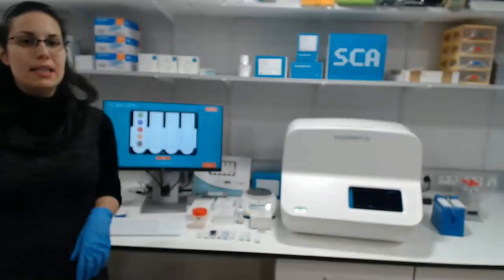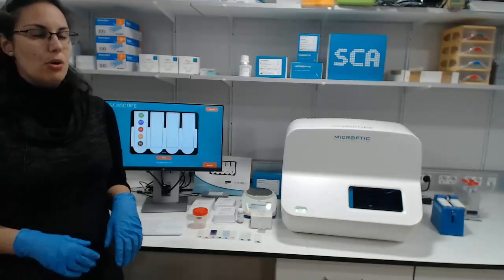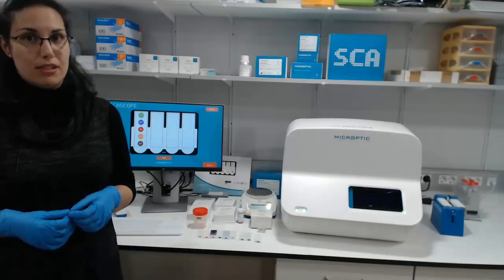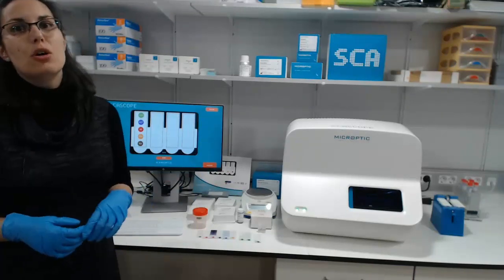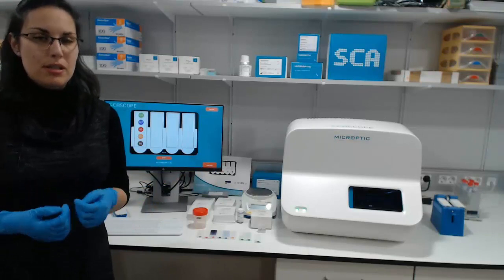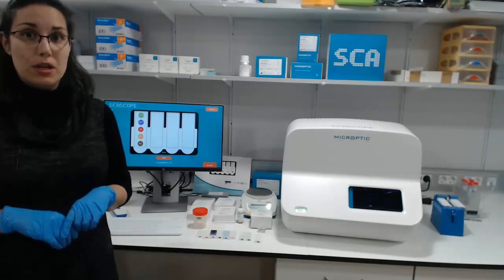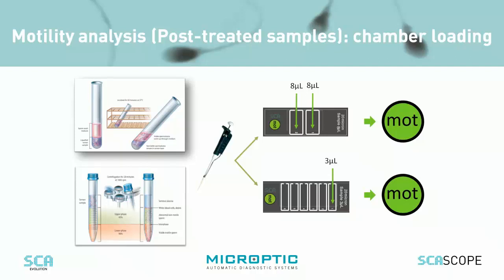For laboratories that are also doing sample treatments, it is important to know that the SCA scope also helps analyze post-treated samples and evaluate the percentage of hyperactive sperms. To do that, we will use counting chambers with a depth of 20 microns. This is important because we normally use chambers of 10 microns depth for evaluating fresh semen samples, but when sperms are treated and activated, they need more space for swimming freely and therefore require a deeper 20-micron chamber.